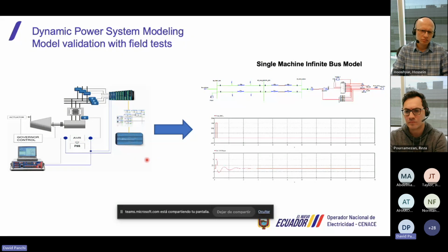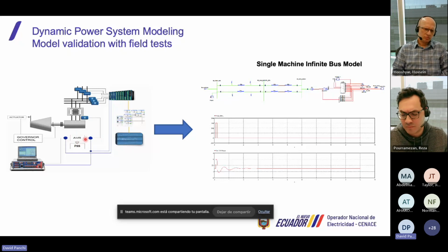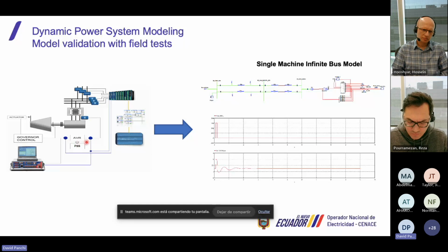With all the data, we have an optimization algorithm that in PowerFactory validates the parameters. The parameters in the AVR are the lead-lag blocks and the time constants. In the governor, they are the gains and the PID constants. We identify these parameters and try to match the field response with the simulation response. The optimization algorithm does several iterations to match these two signals, the simulation signals and the field signals, and moves these parameters, the time constants and PID constants. So, okay, I hope I answered your question.